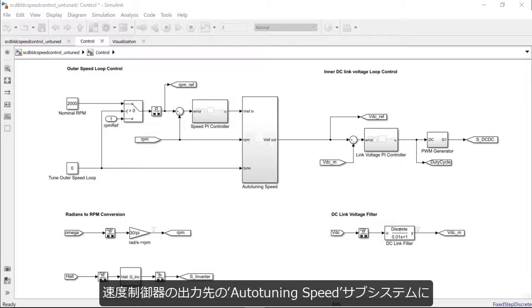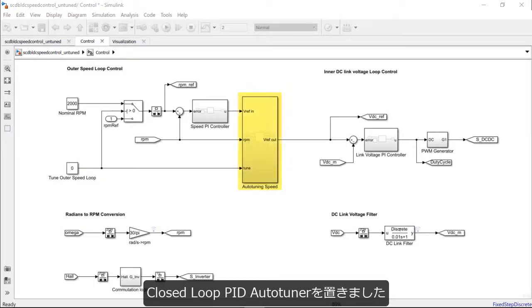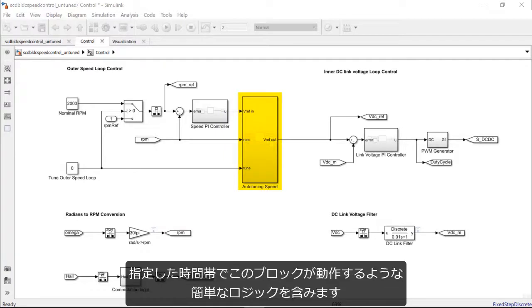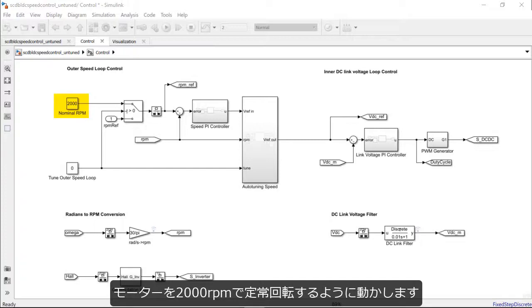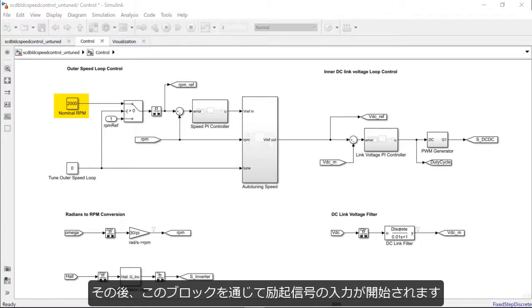Here, we have placed the closed-loop PID auto-tuner after the PI block in a subsystem called auto-tuning speed and included a simple enabling logic to enable this block during a specific time of the simulation. We have chosen a nominal speed of 2000 RPM to which the motor ramps up to and attains steady-state operation before we start injecting excitation signals through this block.